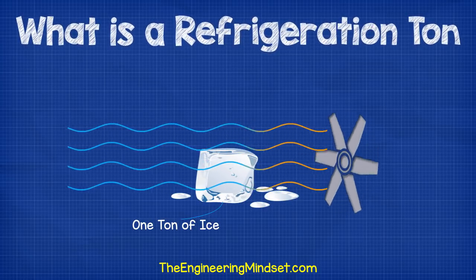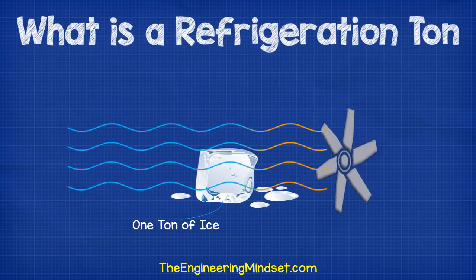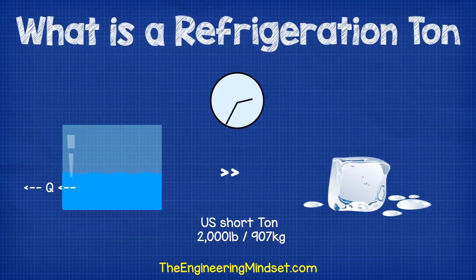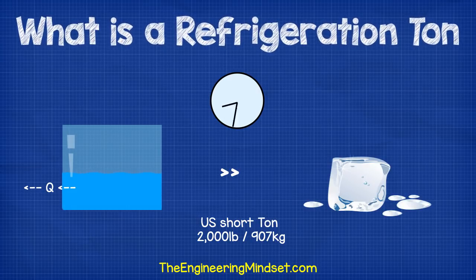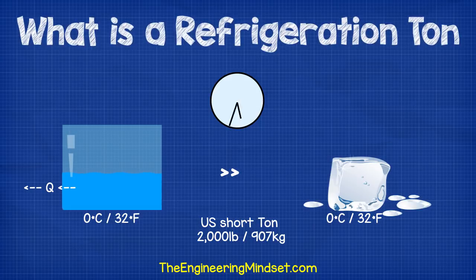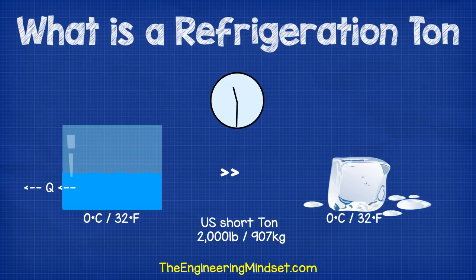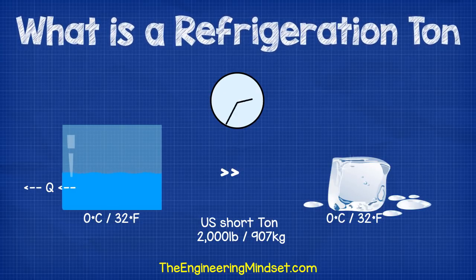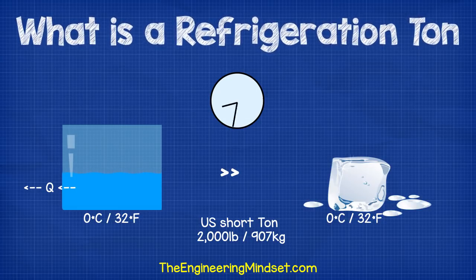The equivalent amount of cooling later became available through vapor compression refrigeration machines. So a ton of refrigeration is how much heat needs to be removed from a US short ton of water to turn it into ice within 24 hours. This is only for the latent heat, so the water would need to be at 0 degrees Celsius, 32 degrees Fahrenheit, and the ice would then also still be at 0 degrees Celsius, 32 degrees Fahrenheit. This is only the energy to cause a phase change of the water — to turn it from a liquid into a solid, so from water into ice. If the water was at room temperature then you would need to remove more heat to bring it down to 0 degrees Celsius, 32 degrees Fahrenheit, before it can be turned into ice.